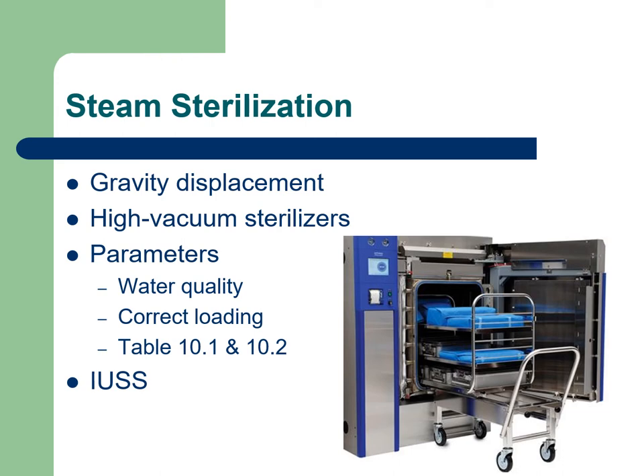When the items come out, they need to sit in sterile processing for a while because they're too hot to take out into the rest of the facility. If you've ever had sunglasses on and walked outside when it was hot and humid, coming from somewhere cool, you immediately get fogging on your glasses. The same thing happens with these instruments. If they're super hot and you put them on the shelf, that can cause condensation, and we end up with water or wetness in our trays. That's not good, because wetness leads to strike through.